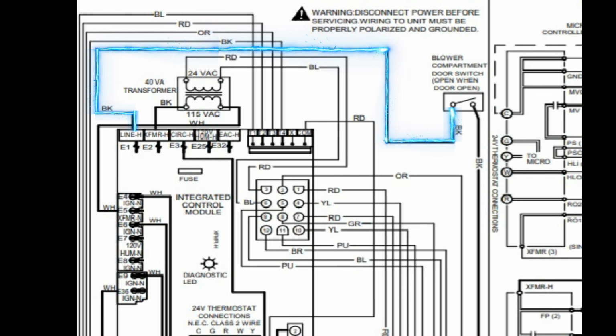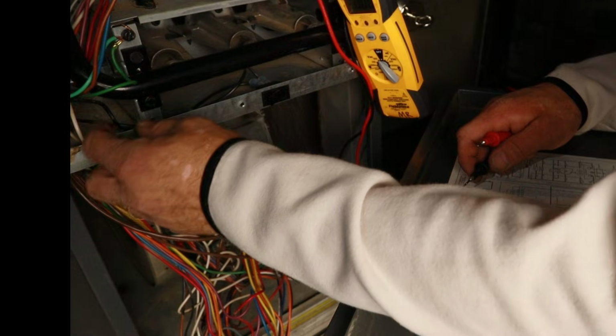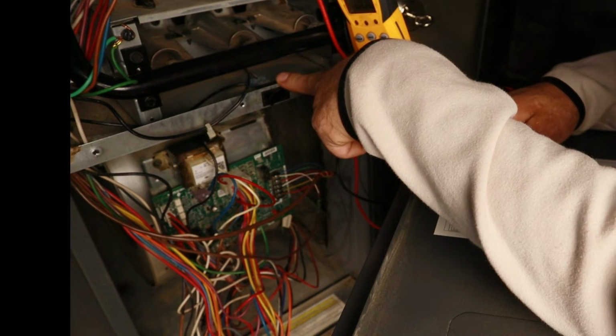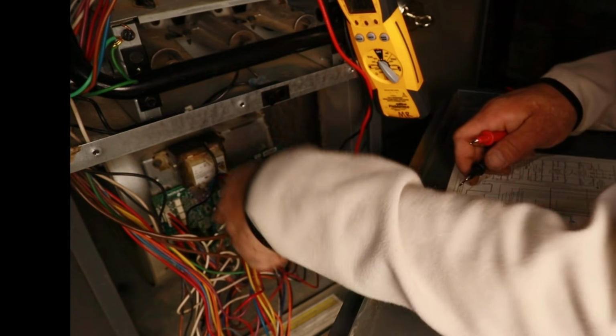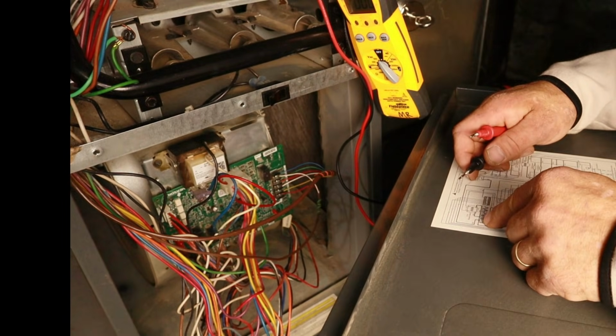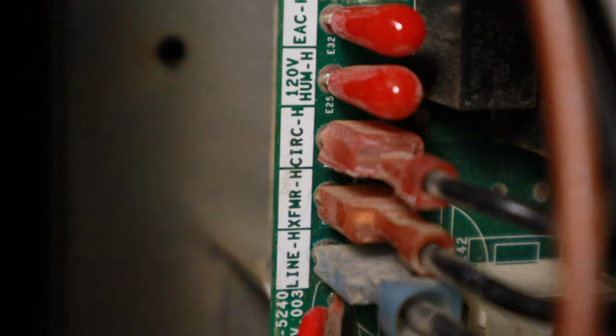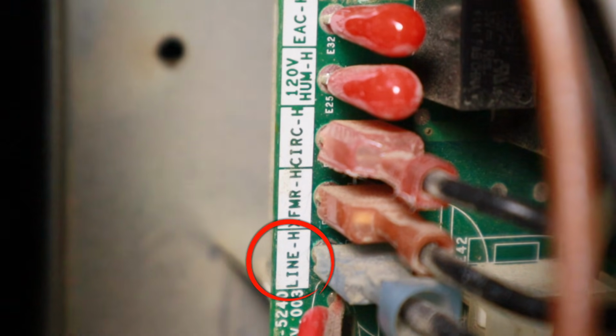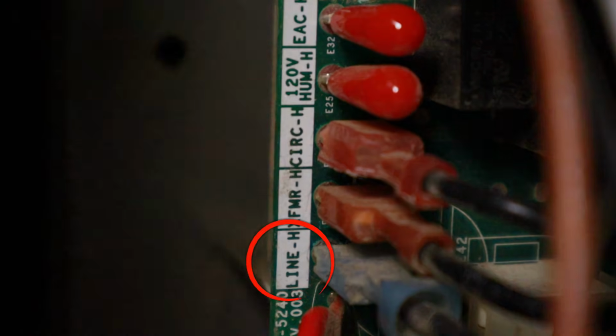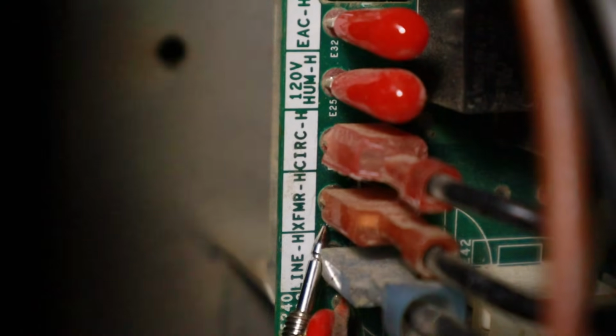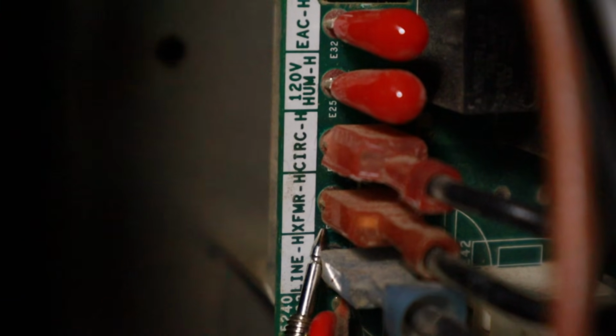Now on the schematic, we follow it and we can see it goes down to line H block, and that is on our integrated control module. So this whole square here is our control board. So if we take this black wire, this is the black wire coming from our switch into the door switch. We have our other black wire coming off that door switch and going down to our control module on the line H terminal. So you can see on our close-up here, we have our line H terminal with that black wire coming in. So if I were to go ahead and put my probe on there, go to ground, I'm not reading anything right there.